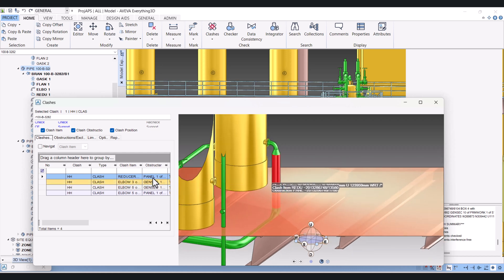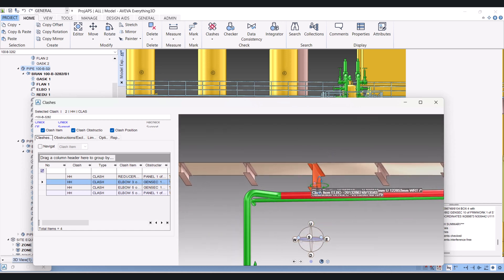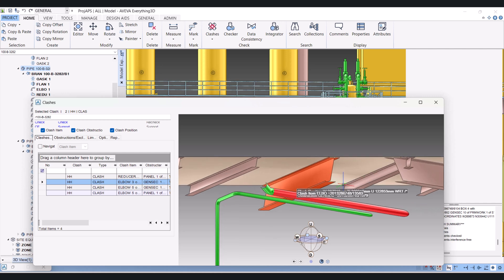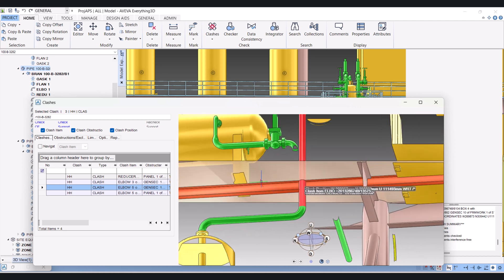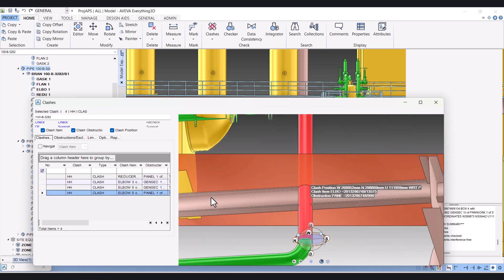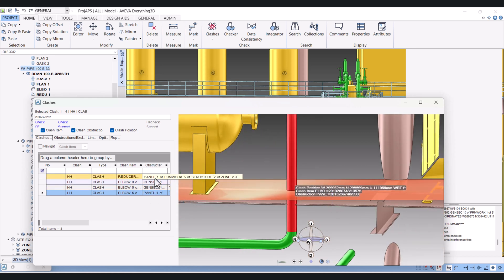This clash is showing me the panel, and this clash can be avoidable because this is the deck plate, so this is OK. Second one, we will check the elbow — you can see that the elbow is clashing with the structural beam. The third one is also clashing with the structural beam, and this elbow is showing a clash with the panel. So these panel clashes we can avoid, but the ones clashing with the structure — these clashes we have to resolve.